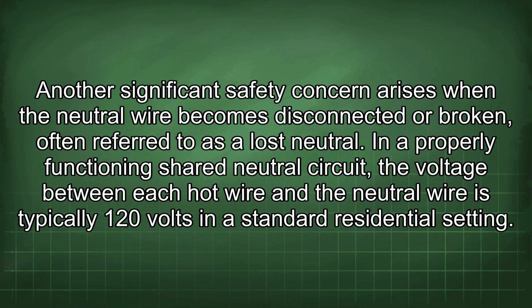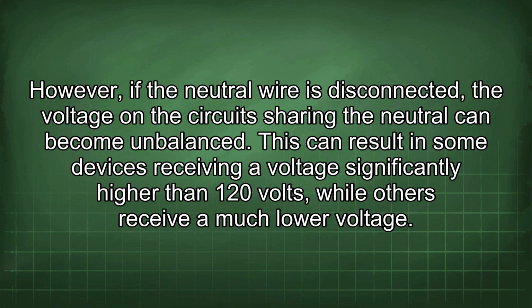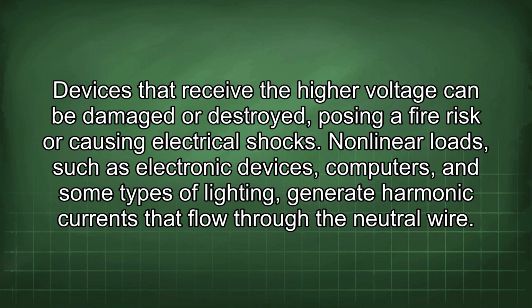Another significant safety concern arises when the neutral wire becomes disconnected or broken, often referred to as a lost neutral. In a properly functioning shared neutral circuit, the voltage between each hot wire and the neutral wire is typically 120 volts in a standard residential setting. However, if the neutral wire is disconnected, the voltage on the circuit sharing the neutral can become unbalanced. This can result in some devices receiving a voltage significantly higher than 120 volts, while others receive a much lower voltage. Devices that receive the higher voltage can be damaged or destroyed, posing a fire risk or causing electrical shocks.